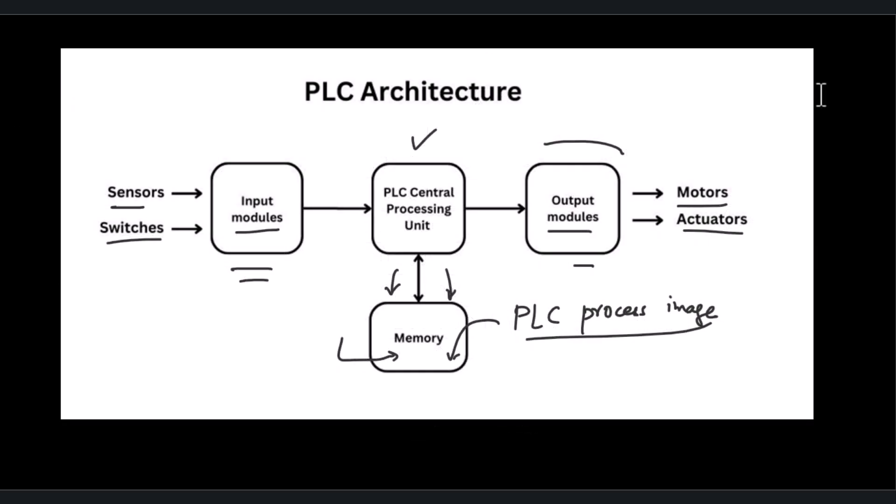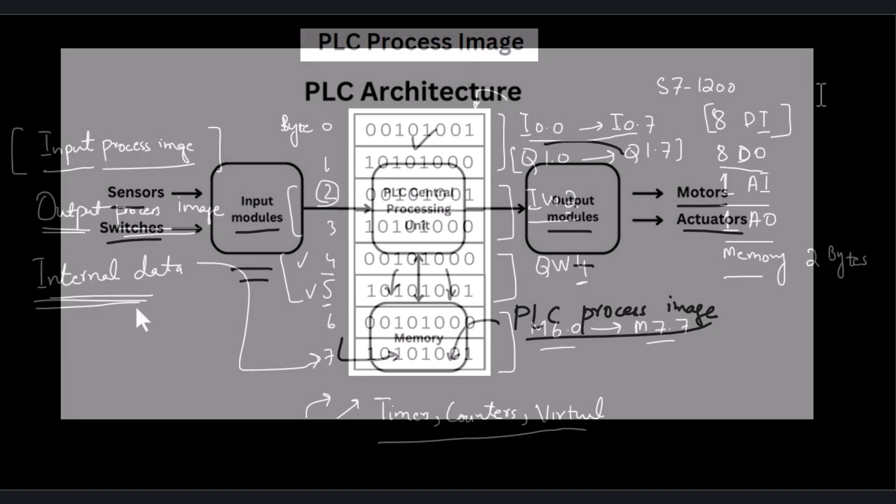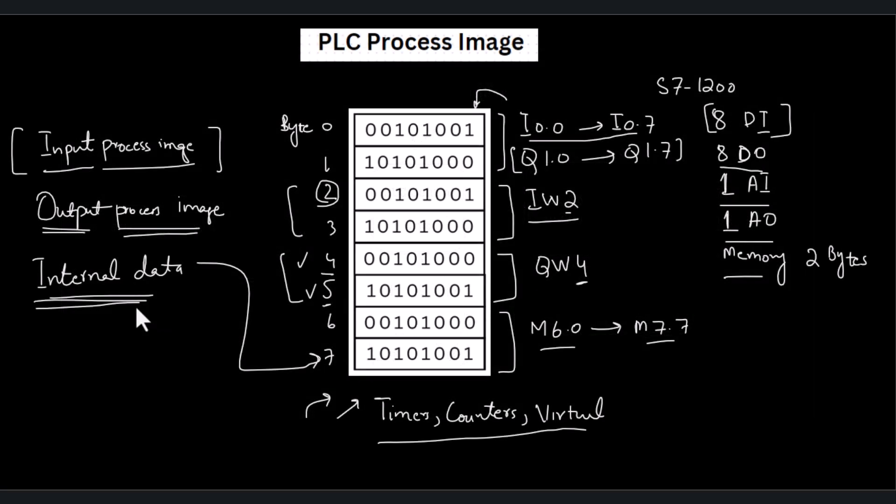It is important to understand that the PLC process image is updated with every PLC scan cycle. The CPU of the PLC reads data from the input modules coming from sensors and switches and updates the input process image. It also processes the data to generate outputs and updates the output process image, while continuously updating the process image with the internal data of the program.